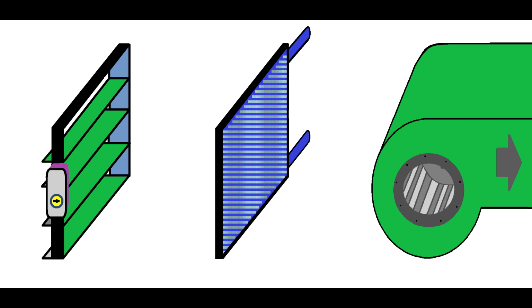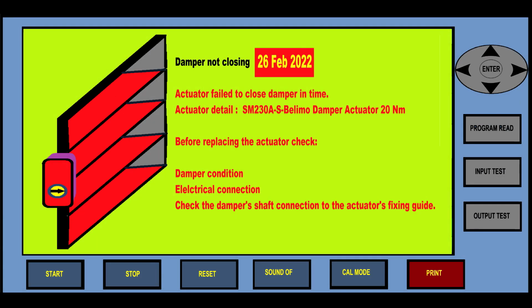This system requires a functional interlock because there's only one damper. If the damper is not opening, the motor won't have any air to pull and it will look again like a blocked vacuum cleaner. So when the damper opens, it will instruct the fan to run. So this is the interlock between the damper and the motor. If you have a damper failure, obviously the motor will not run. And let's go a little bit deeper. Let's see how this damper works.